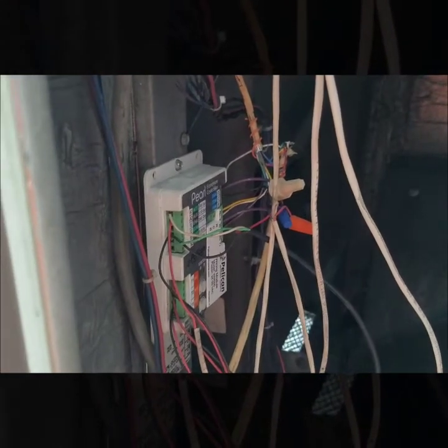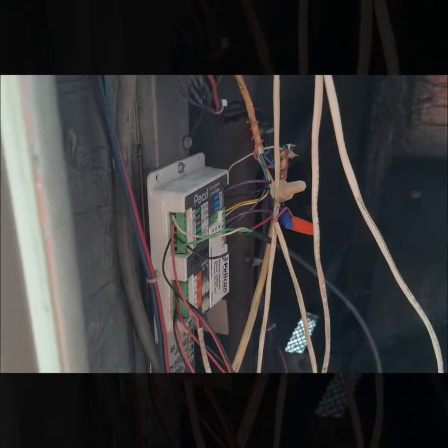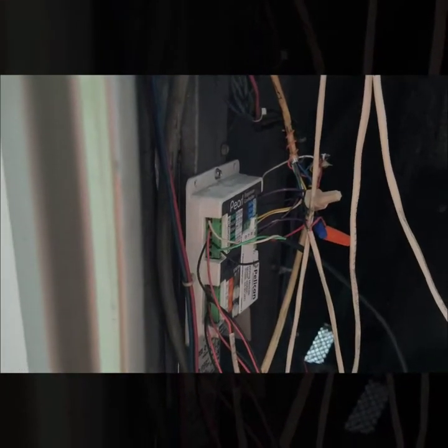So it's a known issue with Pelican. They've kind of told us that it's common in the Trane. For some reason, only like the 10 to 15 year old Trane equipment, there's something with how the Trane equipment's made that makes them act up. So if you run into an issue where they're welded closed, that might be something to look at.